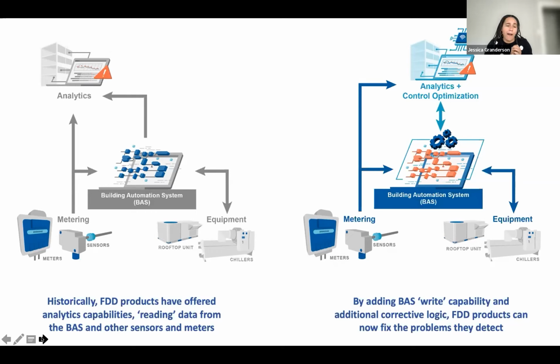On the left, I show the historic architecture of these systems. The analytics reads data from equipment and control systems. It operates in a passive manner. It analyzes the data and surfaces that for a user. What we've done is open up two-way capability between the analytics and the building automation system. So we now no longer simply read from, but also can write back to the control system. We've also complemented the fault detection and diagnostic logic with corrective logic that's based on building controls and engineering principles. So in doing that, we've brought together analytics and control optimization.